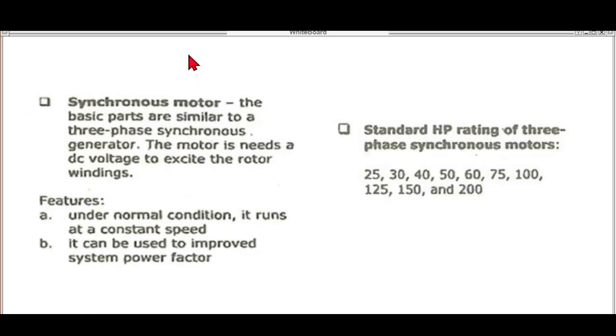Okay. Synchronous motor is the type of motor which runs at a constant speed. So they are basically three-phase motor na constant ang kanyang speed, no? Yung hindi synchronous motor na three-phase motor, tawag ay induction motor. Okay. So because all of those motors work using the principle of induction or electromagnetic induction. So the features of this synchronous motor, it runs under normal conditions at a constant speed and it can be used to improve the system power factor. So the standard horsepower of our motor is yung pinakamababa niya is 25 habang yung pinakamalaki naman is 200.